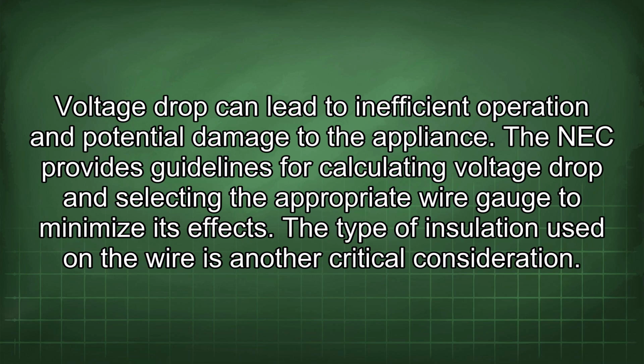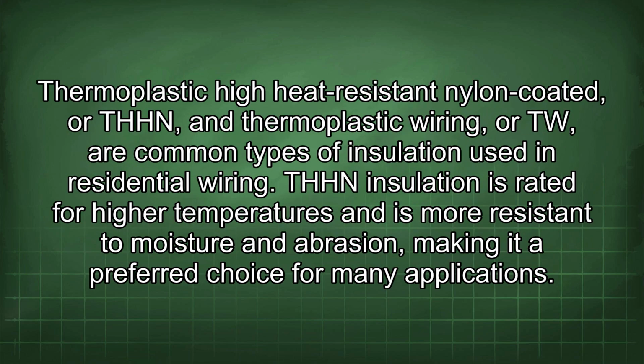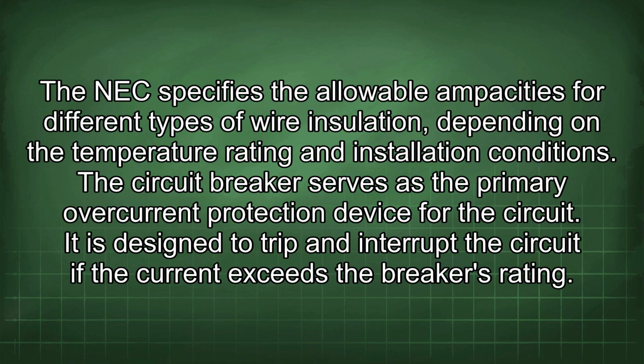The type of insulation used on the wire is another critical consideration. Thermoplastic high heat resistant nylon coated, or THHN, and thermoplastic wiring, or TW, are common types of insulation used in residential wiring. THHN insulation is rated for higher temperatures and is more resistant to moisture and abrasion, making it a preferred choice for many applications. The NEC specifies the allowable ampacities for different types of wire insulation depending on the temperature rating and installation conditions.